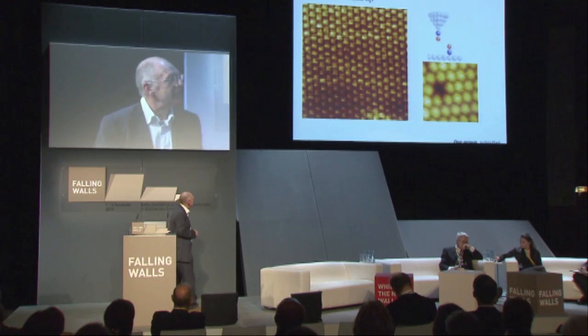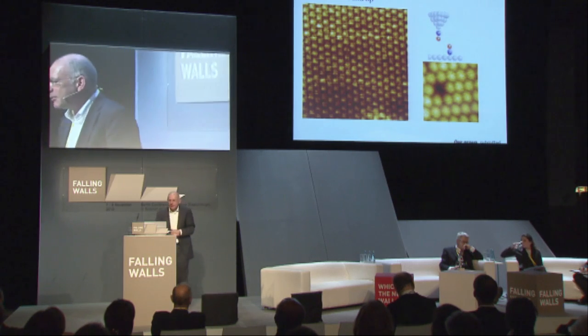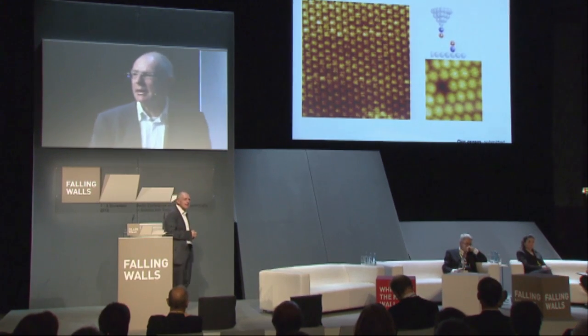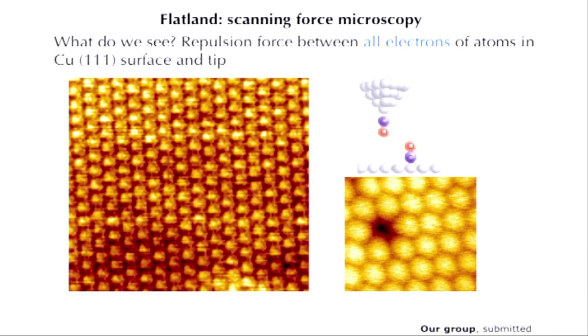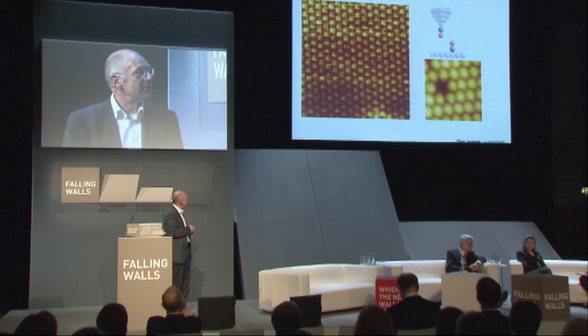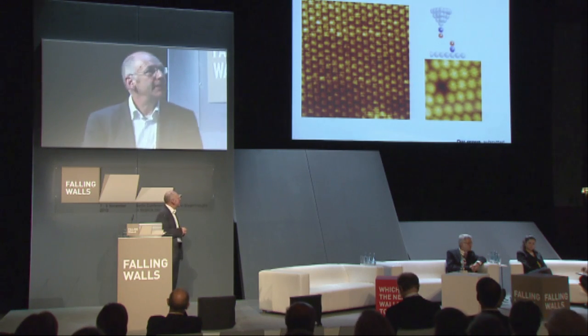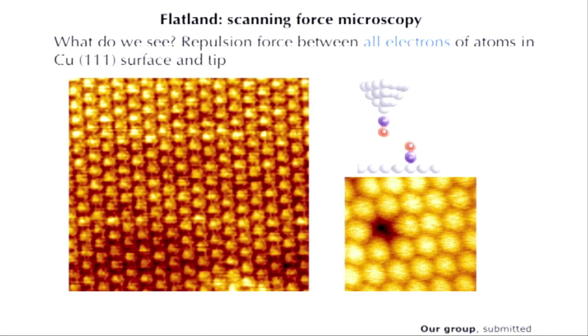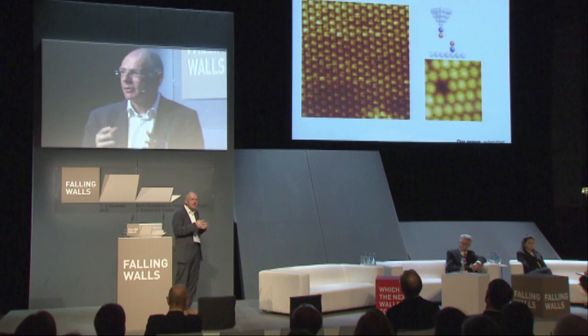Now a second example from our group — the famous copper surface. Here we use the tip not for measuring the tunneling current, but to measure the force between the last atom on the tip and the surface. We see an ordered array, and this must be the copper atoms. The difference is that we measure the force and not the tunneling current, so we use another signal. A little secret: to make the picture sharp, we have added a carbon monoxide molecule bonded to the last atom of the copper tip, because it's a much sharper and stiffer probe.